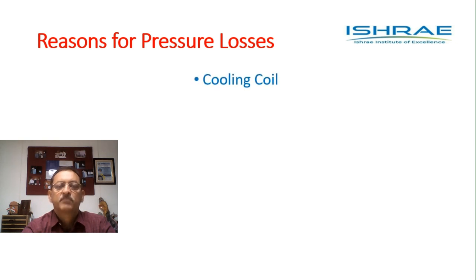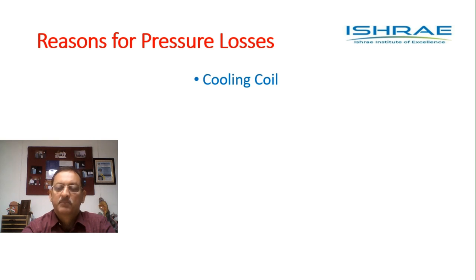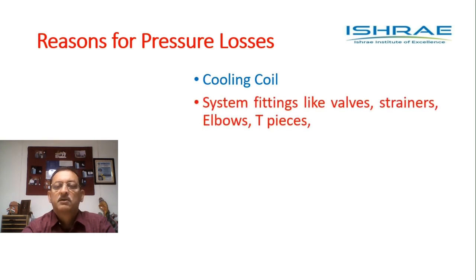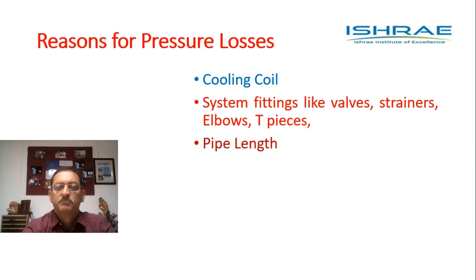The pumps should be capable of overcoming all these pressure losses. Pressure losses occur in the cooling coil because it has several bends, and when water flows through these pipes it encounters a lot of resistance. There are many system fittings such as different kinds of valves, strainers, elbows, and T-pieces used in the system — each one of them causes a certain amount of pressure loss that we need to estimate and add up.